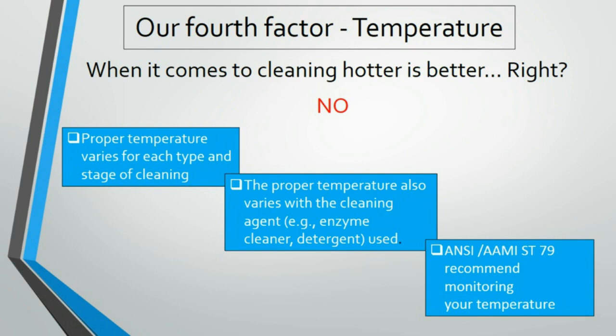The proper temperature also varies on your cleaning agent, because at the wrong temperature, those enzymes, again, the things in the cleaning agents and the detergents that we want to help us, we can actually harm those enzymes with the incorrect temperature of our water. And AAMI ST79 recommends monitoring your water temperature for those exact reasons.